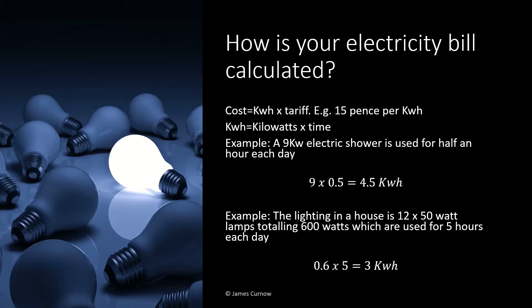For another example, if you imagine the lighting in a house is made up of 12 fifty-watt lamps totalling 600 watts, and the lights are used for 5 hours per day, we can convert the 600 watts into kilowatts by dividing by 1000, and the equation becomes 0.6 multiplied by 5 which comes to 3 kilowatt hours. The lighting in this example uses much less energy than the electric shower, however the lights are used for longer each day, so it is possible to reduce energy consumption by using energy efficient lighting such as LED lighting.